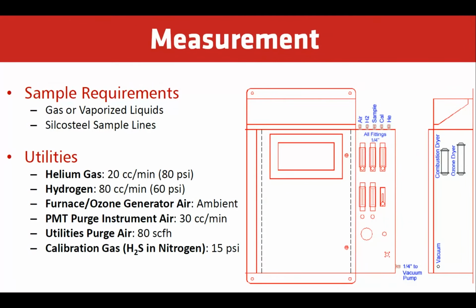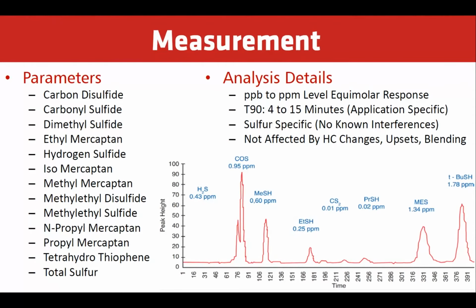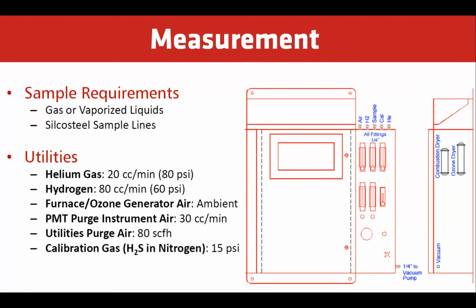Hydrogen flows roughly around 80 cc's a minute. We require 60 psi per utility. The furnace and ozone generator air is done just from ambient. The PMT purge instrument air is roughly around 30 cc's a minute. The reason for that is, because the PMT is being cooled, we try to keep any kind of frost or liquid from building up on the PMT and causing issues with the analyzer.